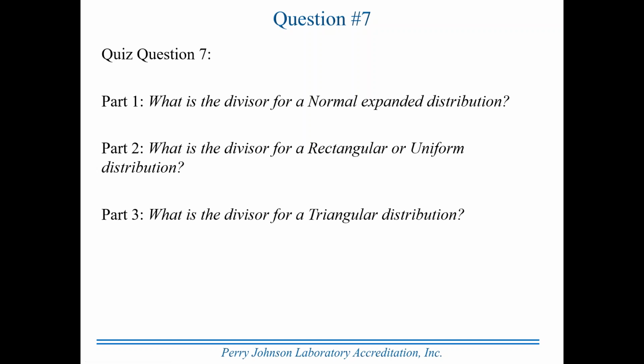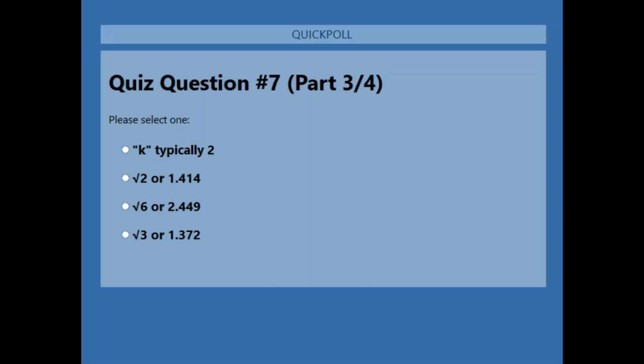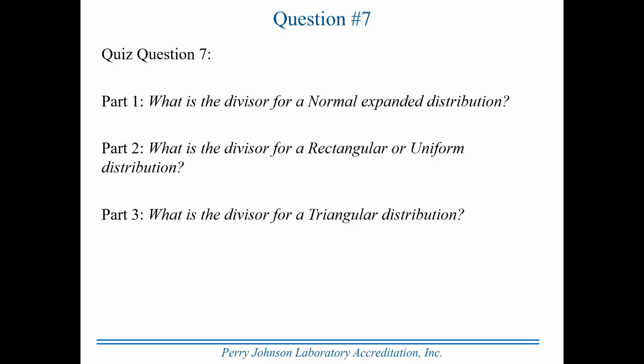Now, for number 3, what is the divisor for a triangular distribution? Let's open the poll and let you pick that one. Okay, we'll close the poll and talk about this one for a bit. The triangular distribution is a distribution that occurs where it looks very much like a normal distribution. It has a peak in the middle, tapers off to nothing across the interval, much like the rectangular or uniform distribution. The difference, though, this one, the divisor, instead of being the square root of 3, it's the square root of 6. Now let's put up the last one. What is the divisor for a U-shaped distribution? Let's open the poll so you can make a selection.